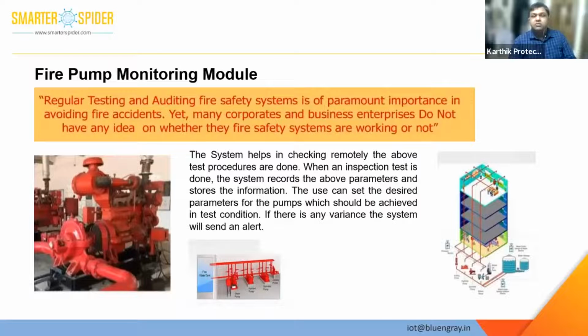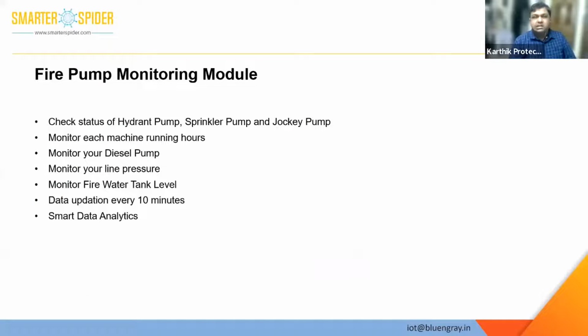The second thing is we found that the water in the fire water tank is used for other purposes such as gardening, cleaning, and other areas apart from fire purposes. So for that, we have a system where we can check the status of the hydrant pump, sprinkler pump, jockey pump, or booster pump, whichever pump is there inside the building. Then we monitor each pump's runtime. For example, no one knows how long the jockey pump is running continuously. Our system can determine how much time the jockey pump is running, and when, and then monitor your diesel pump.